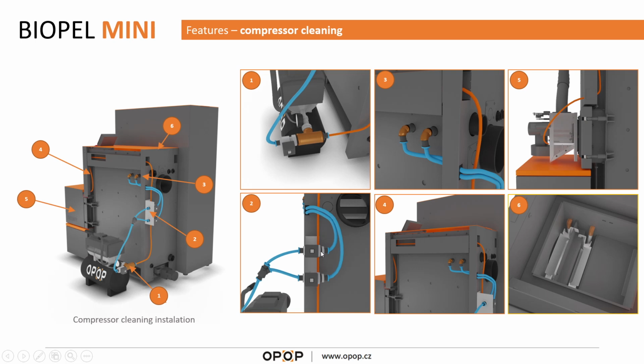Okay, there are solenoid valves connected at the back side of the boiler, and the control unit of the boiler operates these valves. So when you clean the heat exchanger or when you clean the burner, the valves will open and will release the pressurized air to the heat exchanger here and to the burner here. Second solenoid or third solenoid valve is located directly on the compressor, and this solenoid valve is responsible for the burner cleaning. Okay, so this is compressor cleaning.